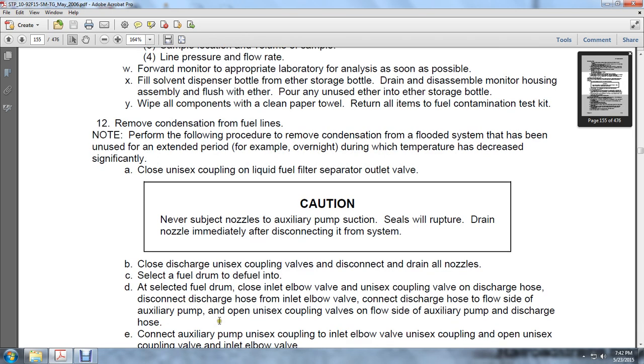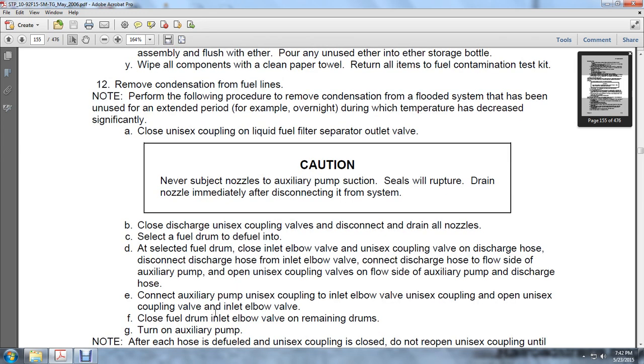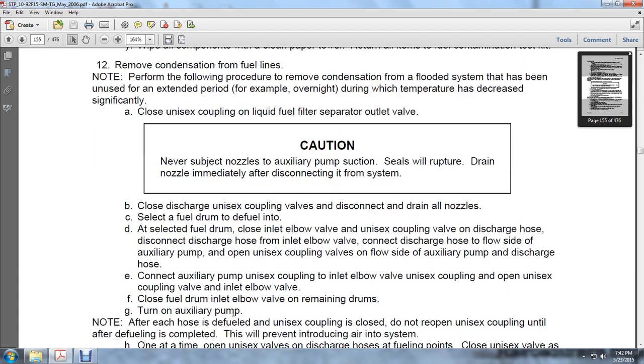Disconnect the discharge hose from the inlet elbow and connect the discharge hose to the flow side of the auxiliary pump. Open the unisex coupling valve on flow side of the auxiliary pump and discharge hose. Connect the auxiliary pump's unisex coupling to the inlet valve unisex coupling, open the unisex coupling valve and inlet elbow valve. Closing the fuel drum inlet elbow valve on the remaining drums, turn on the auxiliary pump.